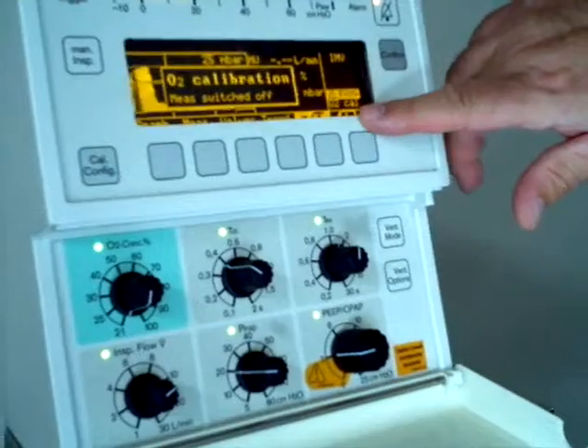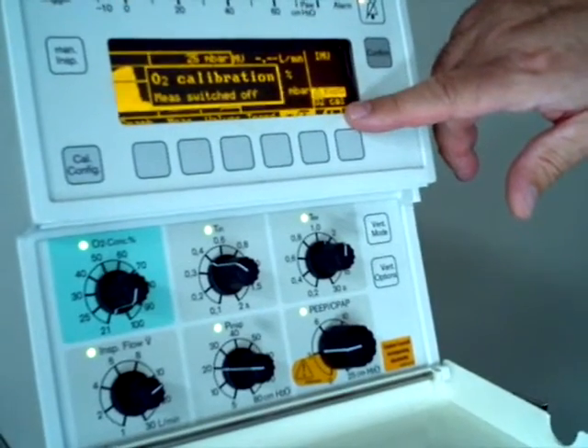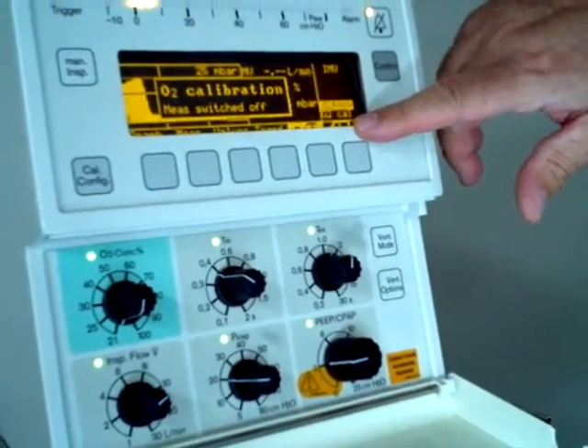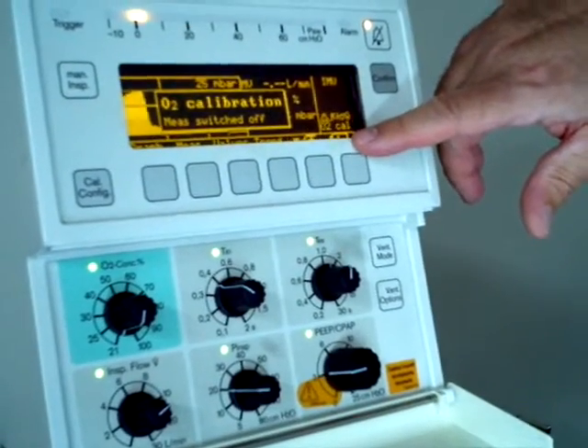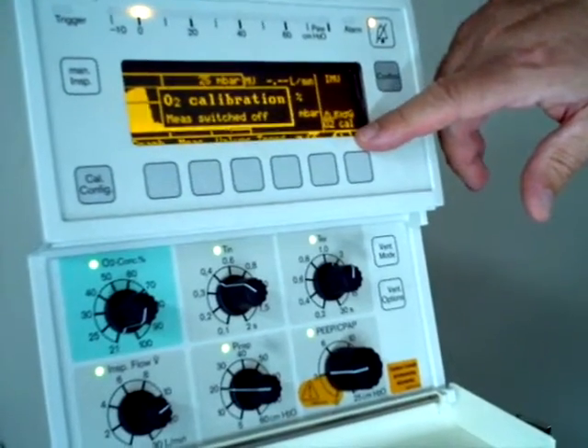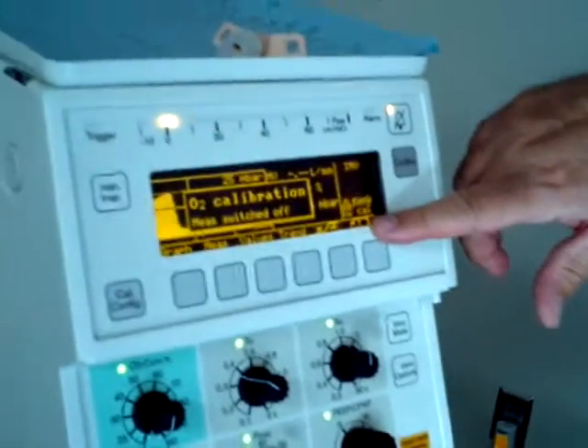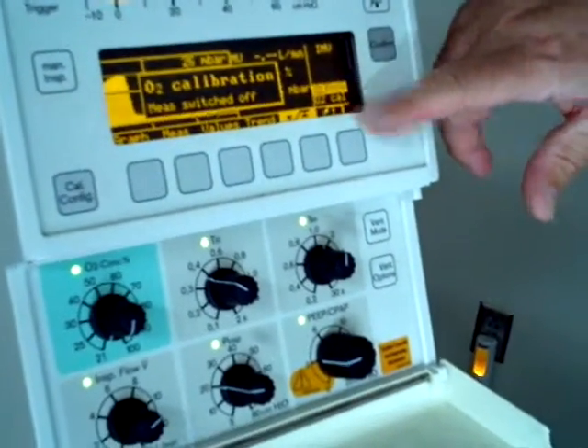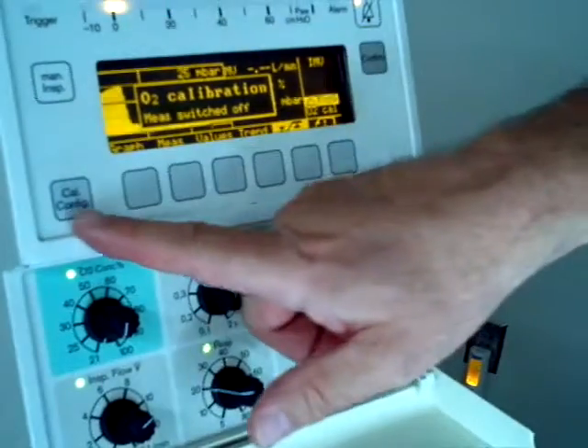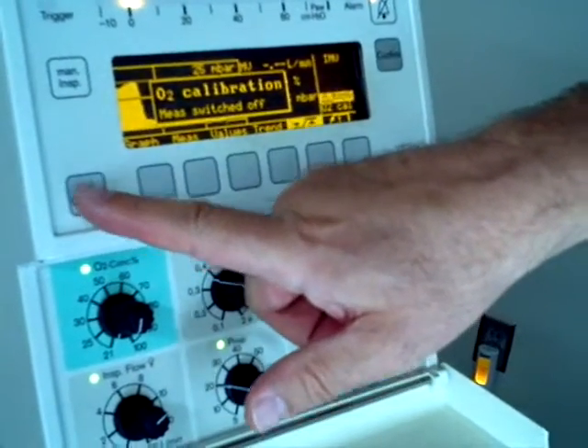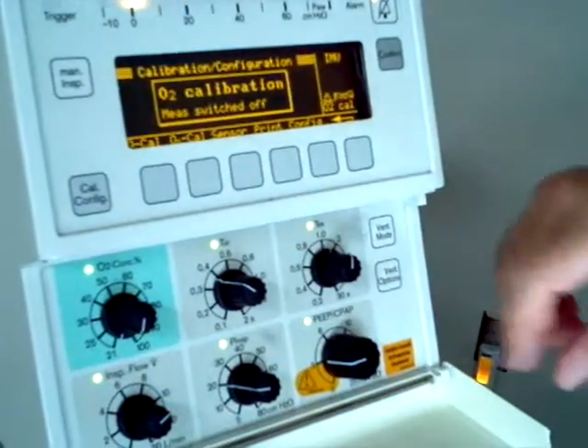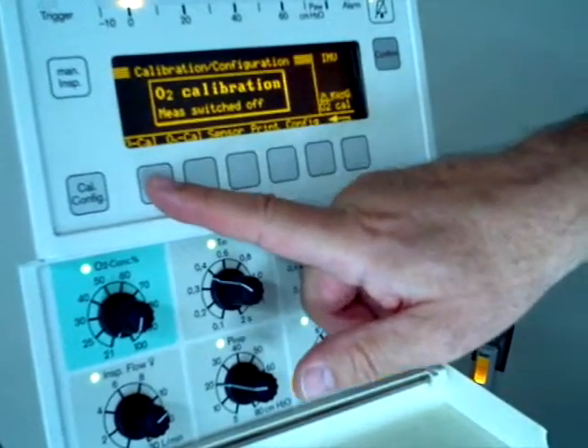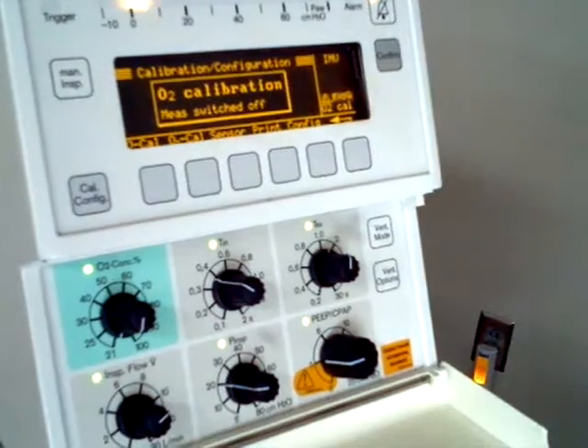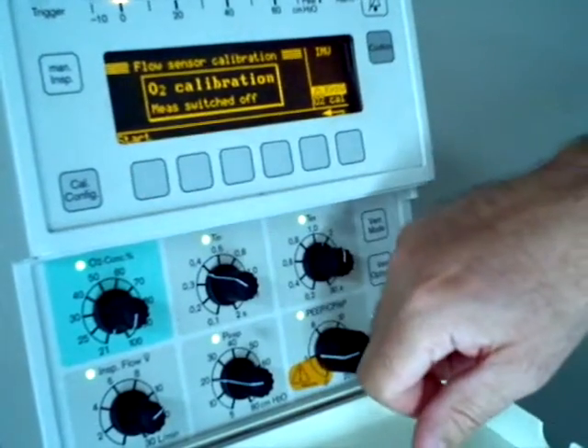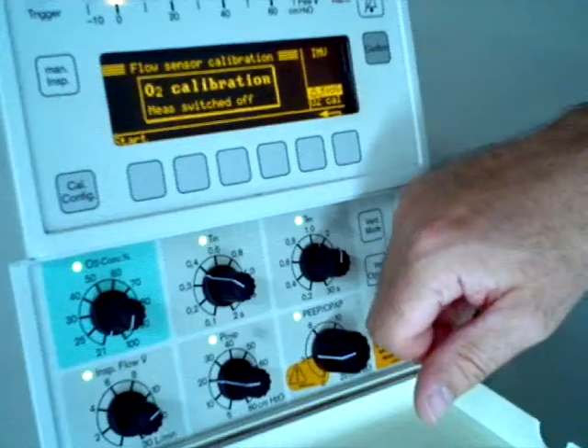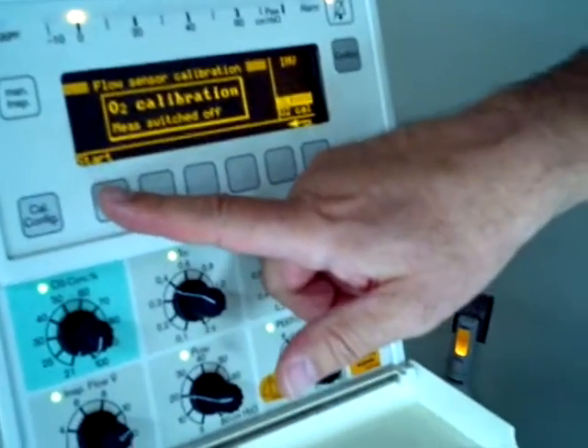Notice here, it's flashing. The flow sensor needs to be calibrated. All right. You won't get any readings on your flow-dependent measurements like tidal volume and things like that until you do that. So to do that, you go to cal config right here, farthest left soft key. Press that under v.cal. Here, and then it will say start right here.